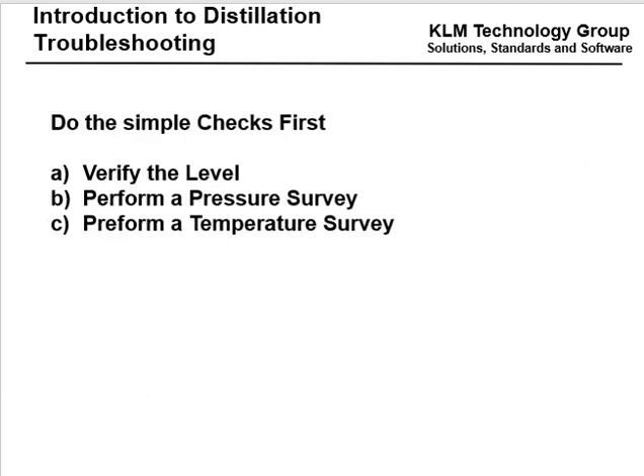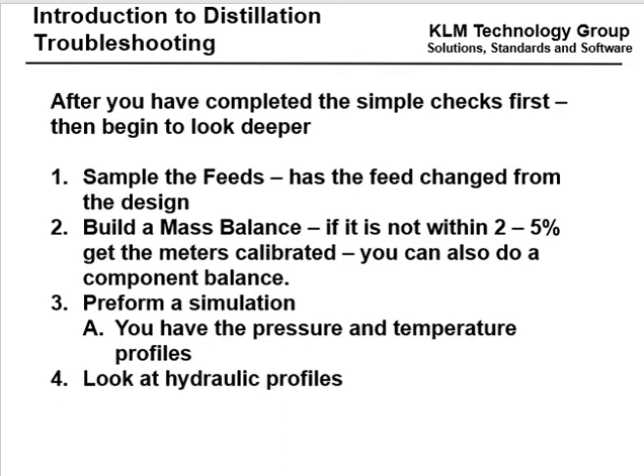Do the simple checks first: verify the levels, perform a pressure survey, perform a temperature survey. If you don't find any problems, look a little deeper. Sample the feeds — has the feed changed from the design? It could be that the new feed can no longer be processed in your existing equipment. Build a mass balance; if it's not within two to five percent, get the meters calibrated. You can also do a component balance — a standard orifice plate has only two percent accuracy, so two to five percent can be a challenge. Then perform a simulation using your pressure and temperature profiles and mass balance to look at the hydraulic profiles and assess whether the trays or packing are designed for your new conditions.